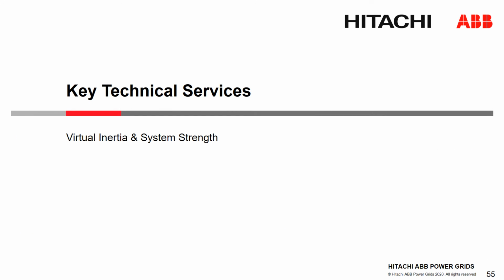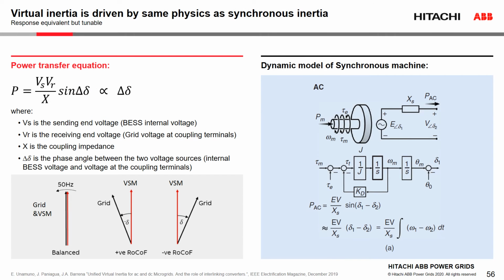This brings us to the key technical services grid forming converters can provide that grid following converters can't, and that's virtual inertia and system strength. This slide describes how grid-forming converters can provide virtual inertia and is an important concept to understand in the context of system strength and how grid-forming converters do not rely on measurement.